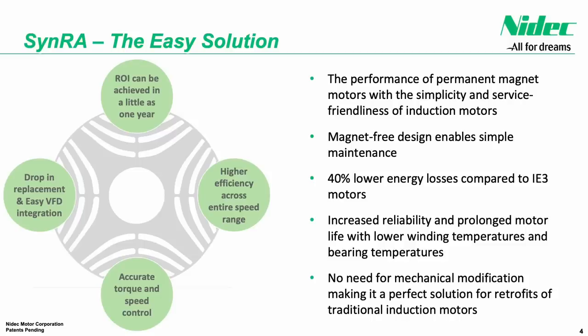SynRA delivers a drop-in replacement for existing installations by maintaining compatibility with volts-per-hertz drives and providing accurate torque and speed control through synchronous reluctance torque delivery. It improves efficiency not only at full load speed but across the entire operating range, reducing energy consumption and providing a return on investment in as little as one year.